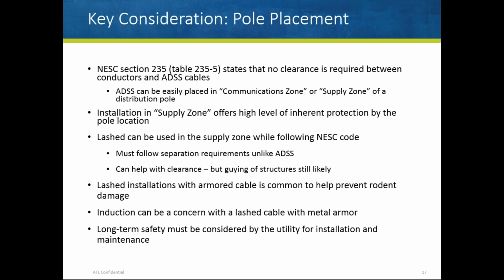A brief note on lashed installations in the supply zone. We have seen this a little bit more frequently, even recently, of utilities interested in using the supply zone with a lashed installation. It's not the same as ADSS, obviously. There are still separation requirements that would start at least 16 inches, I believe. And it certainly could help with clearance, but the pole loading of a lashed installation would not eliminate your make ready costs because guying of structures would still be likely.